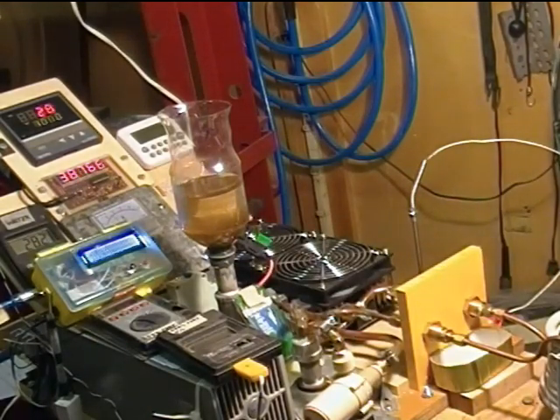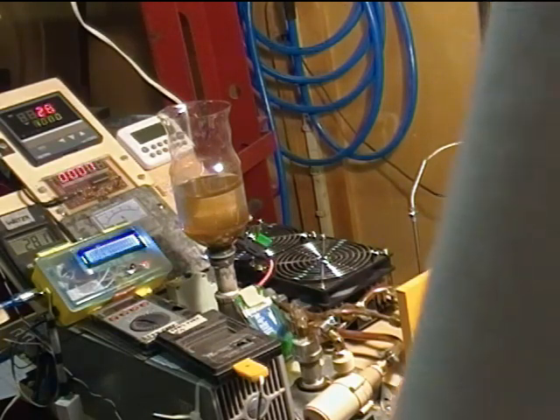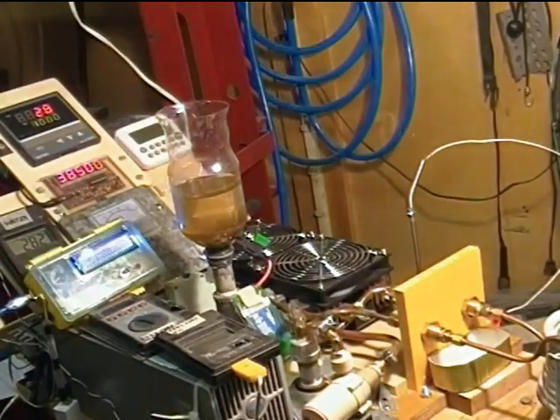Again, if I put the piece of steel in there, things behave normally at 30 amps, normally at 40 amps, 46 amps — getting hot — trip. And that's what's supposed to happen. That's really the guts of this test. We reset, and things are back to normal.